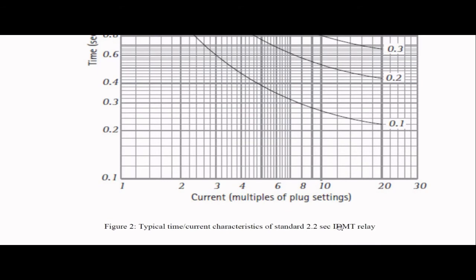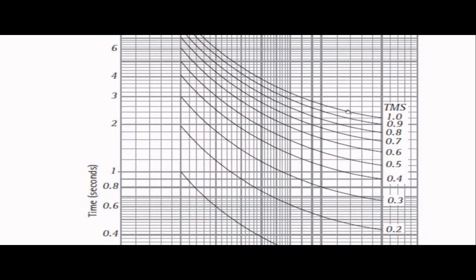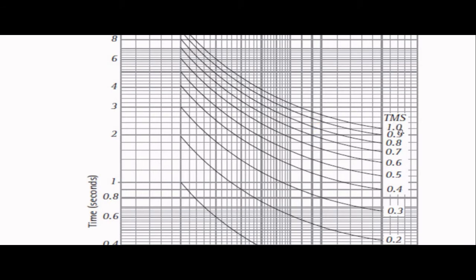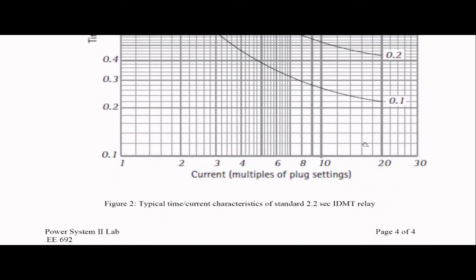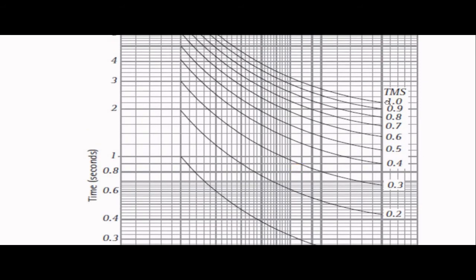Now coming to the definite time: before doing any experiment, from the characteristic curve we can know that if the time multiplier setting is fixed at 1.0, the relay needs at least 2.2 seconds to generate the trip signal. So that's why this 2.2 second is fixed. It is predefined, and it is a minimum time. That's why the name is inverse definite minimum time, because this 2.2 seconds is the predefined minimum time. If the time multiplier setting is fixed at 1.0, this relay must take at least 2.2 seconds to generate the trip signal. It is not possible to generate the trip signal before 2.2 seconds at a setting of 1.0.